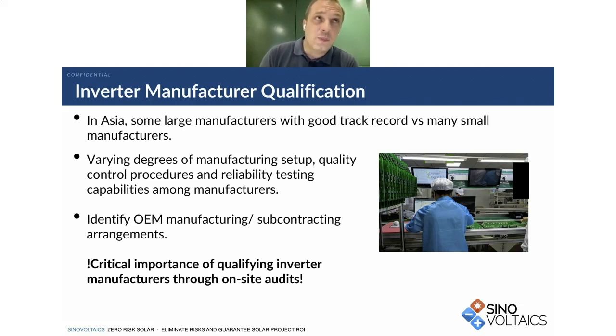This helps to check for issues such as the proper connection of machines, tools and tables to functional grounds, implementation of ESD protective measures, and proper calibration and setting of testing equipment, such as appropriate environmental conditions setup, in order to obtain conclusive results from continuous aging tests.